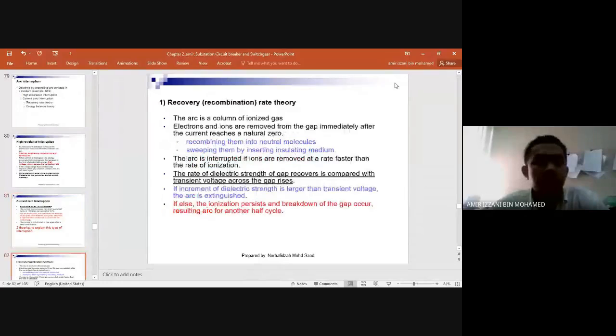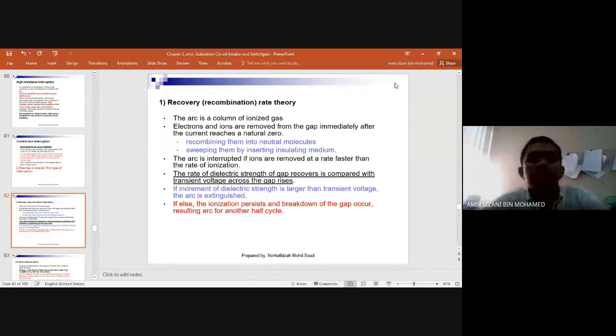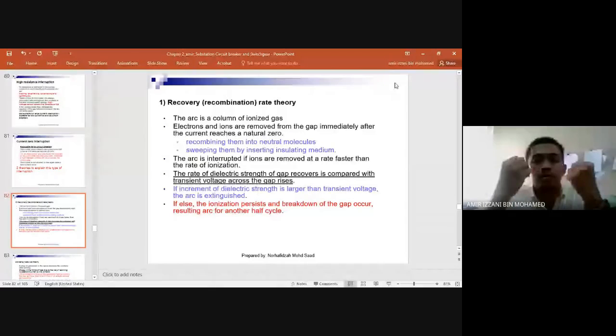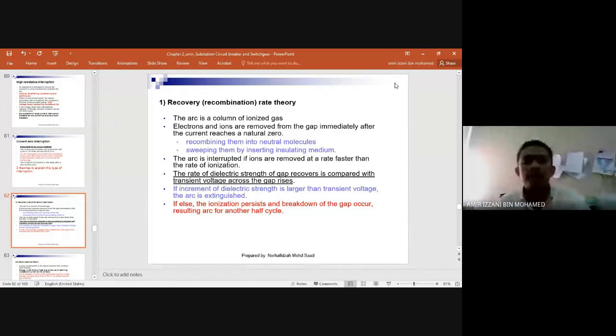So there are two theories to explain this type of interruption. The first one is recovery rate theory, or recombination rate theory. As I explained before, the arc itself is a plasma, which is ionized gas. The gas contains ions: electrons or negative ions and positive ions. So we need to remove those components immediately after the current reaches a natural zero, zero voltage or zero current, by recombining them into neutral molecules, sweeping them by inserting insulating medium.